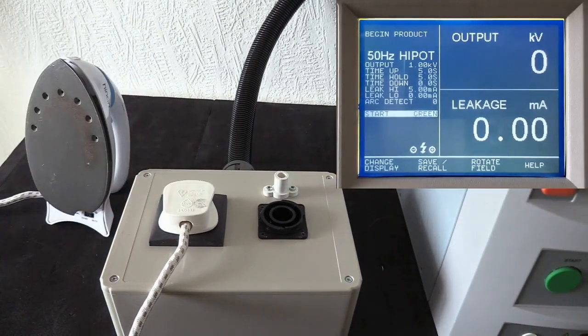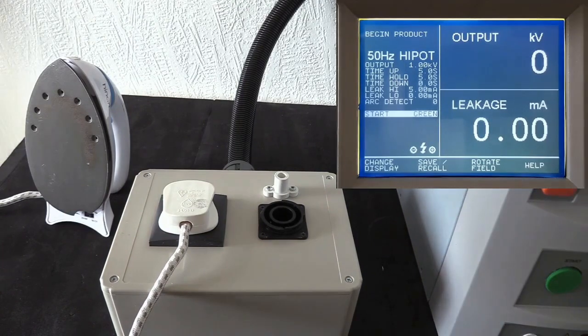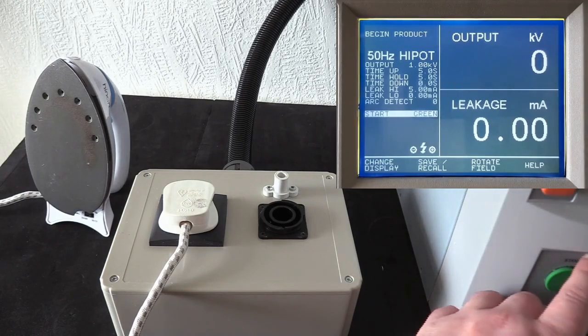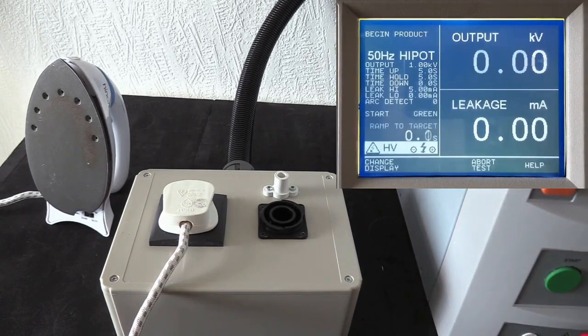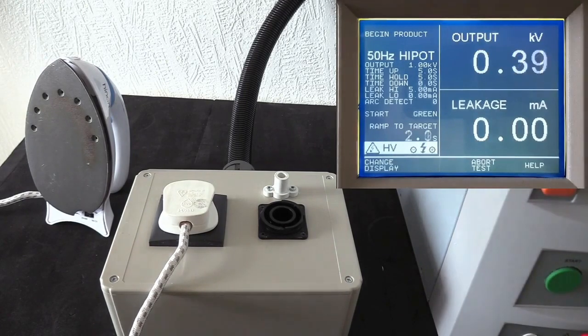In this case, we're going to be performing the test at 1000 volts. We're going to slowly ramp the voltage up over 5 seconds, hold the test for 5 seconds, just to show you what's happening on screen. Typically, this kind of test would be over within a few seconds. So let's perform the test and show you what happens. You can see the voltage rising.